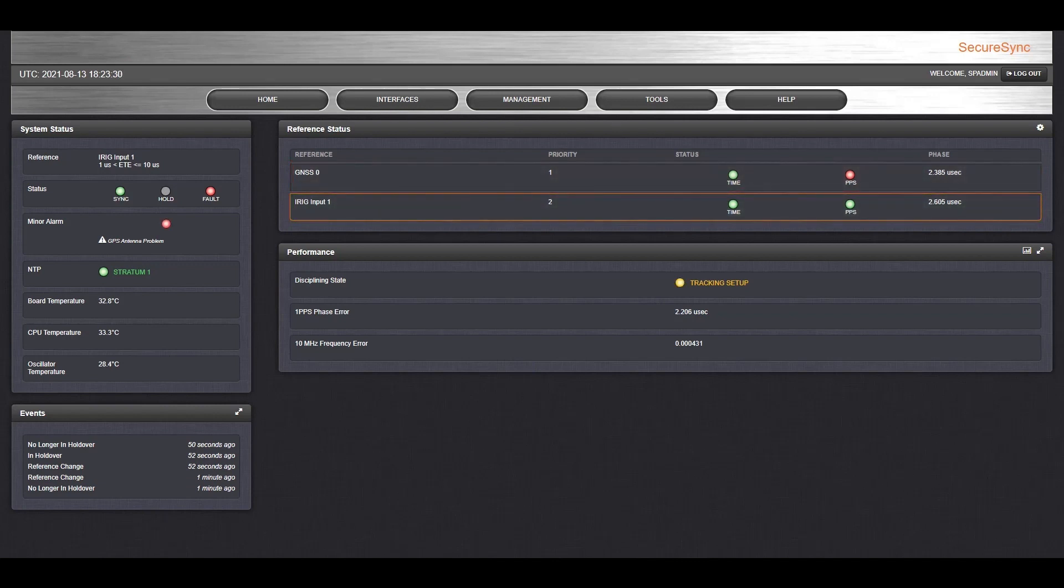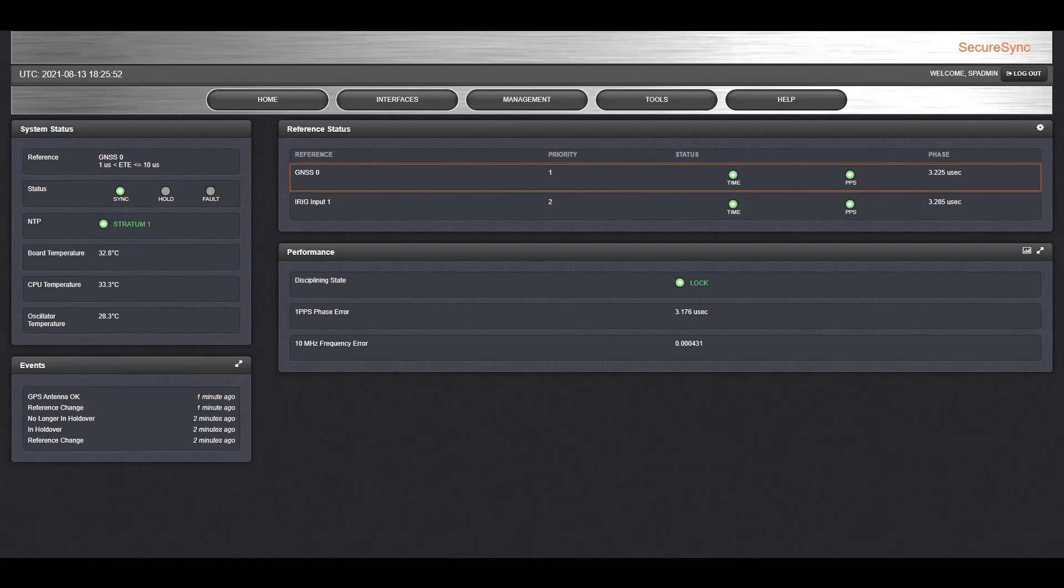Now I will reconnect the GPS antenna. Okay, the GPS is back online, and it has reacquired a lock with the satellites. The SecureSync automatically detected that the antenna had been reconnected, and it's continuing to output highly precise time to the rest of the network.